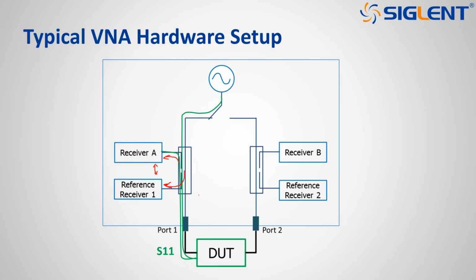If you have a 4-port VNA, you typically have this configuration doubled, but also linked together, since you can measure from port 1 to port 3 or port 4 as well. So it's not just doubling it, there are more connections, but generally the idea of two receivers per port and one source per two ports is the same and similar.